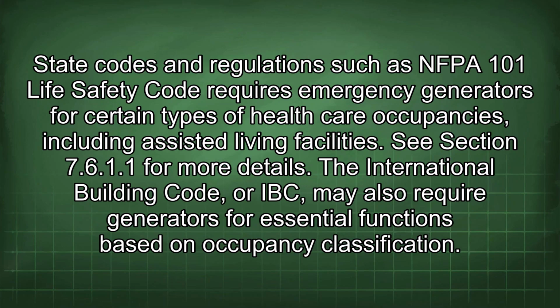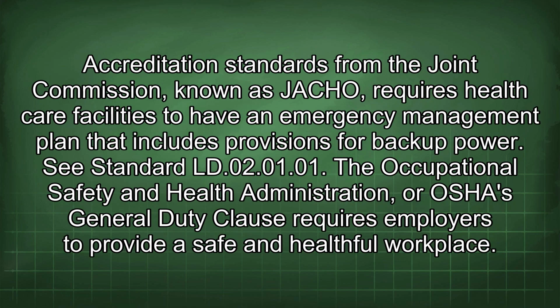State codes and regulations such as the NFPA 101 Life Safety Code require emergency generators for certain types of healthcare occupancies, including assisted living facilities. See Section 7.6.1.1 for more details. The International Building Code, or IBC, may also require generators for essential functions based on occupancy classification. Accreditation standards from the Joint Commission, known as JCAHO, require healthcare facilities to have an emergency management plan that includes provisions for backup power. See Standard LD.02.01.01.